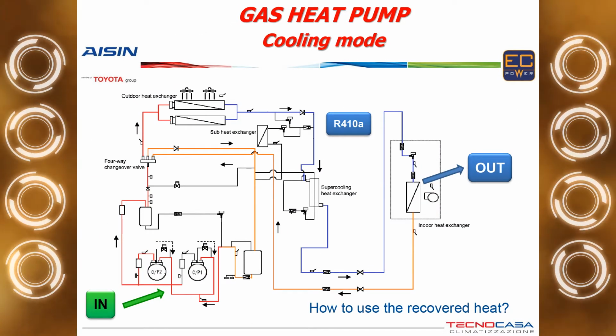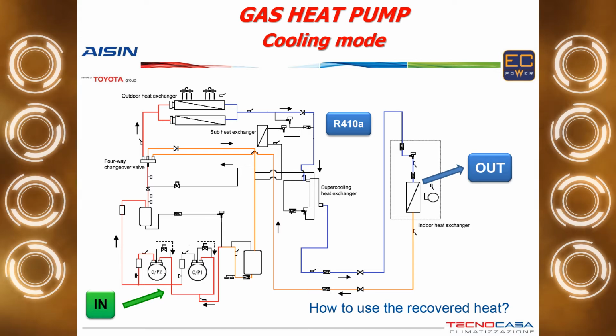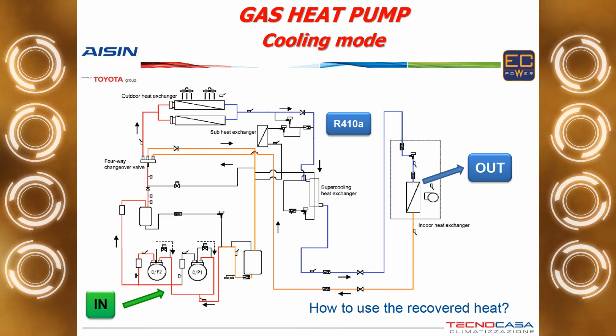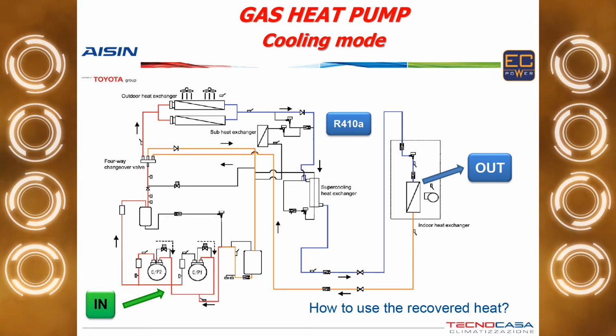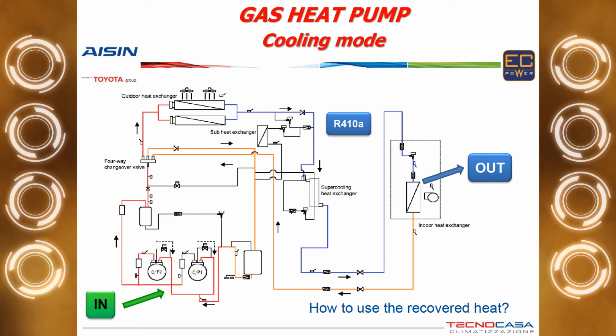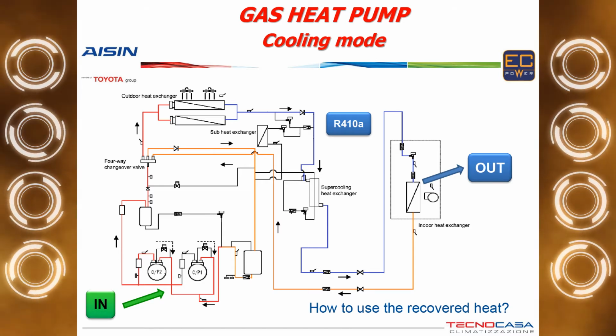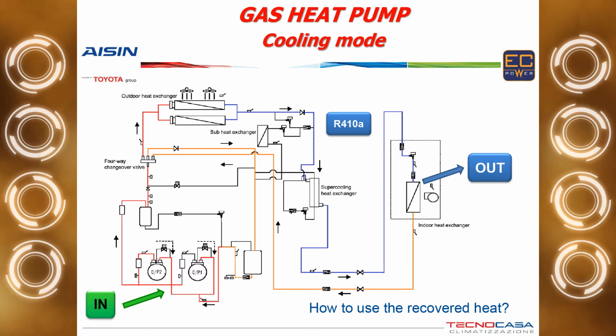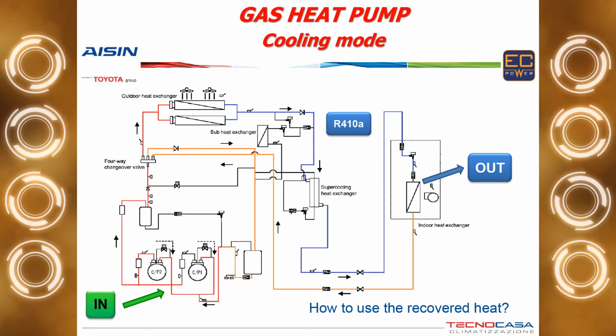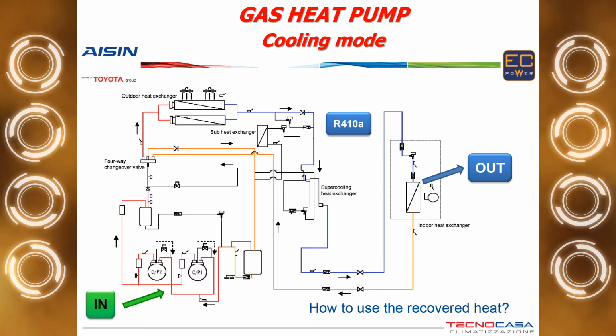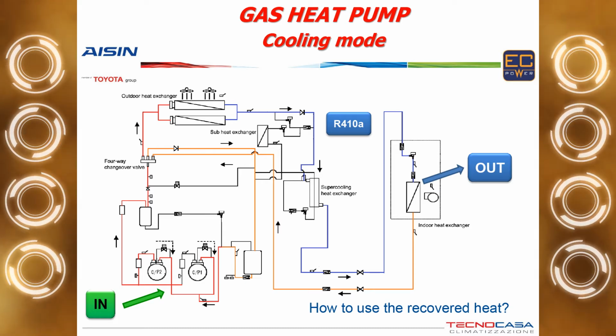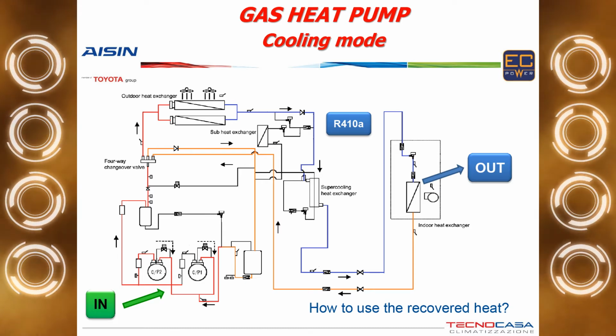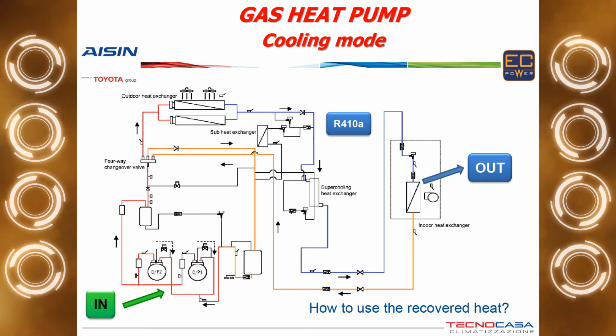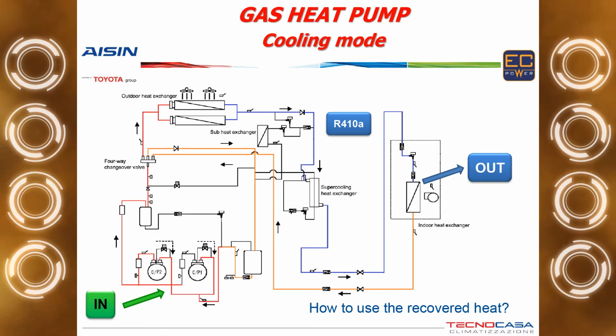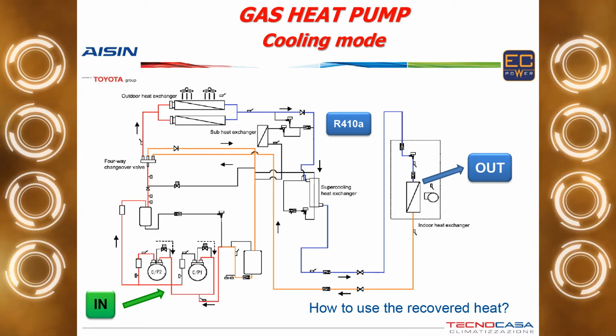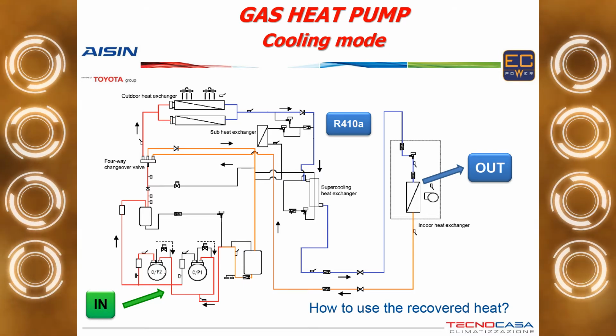So as you can see, the refrigerant system of a gas-driven heat pump is very similar to the refrigerant system of an electric VRV. We have scroll compressors. In this case, we have a variable capacity scroll compressor. So there is a third pipe which allows the recycling of some of the refrigerant to keep the efficiency high at very low revolution speed. As a matter of fact, those heat pumps can modulate down to 20% of their capacity. Then we have a usual four-way valve because the cycle can be reverted from cooling to heating.